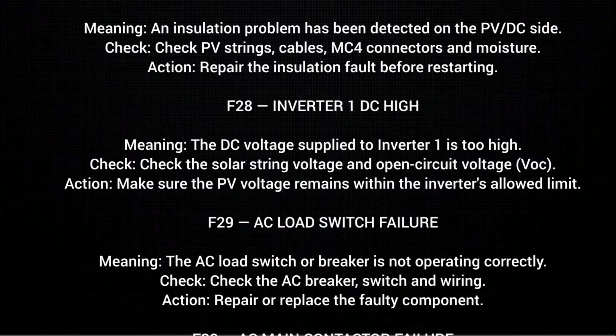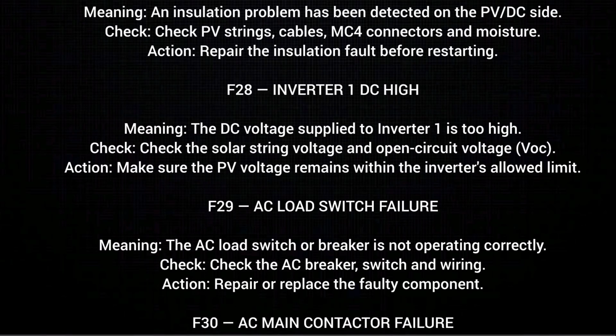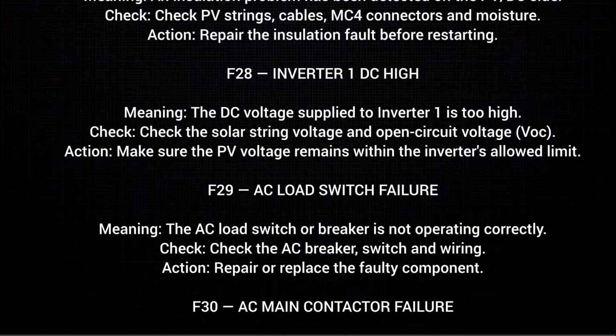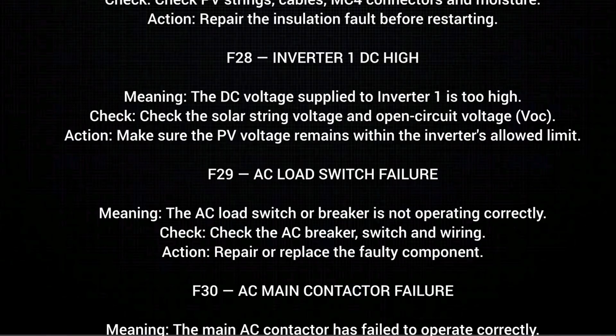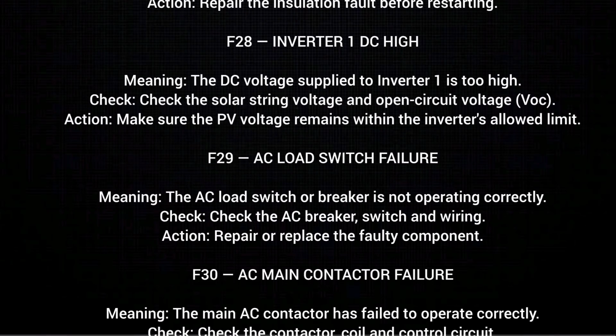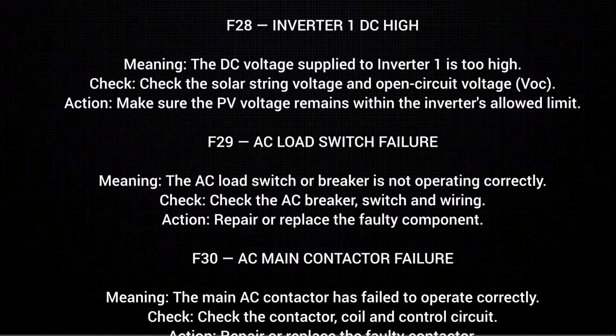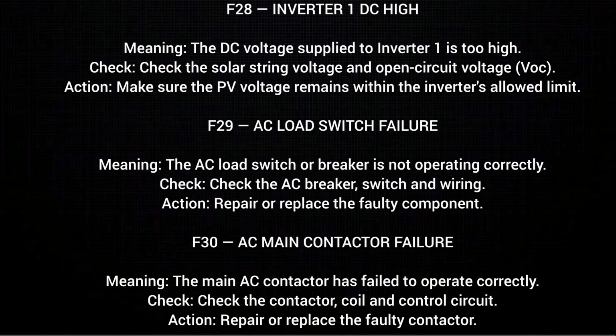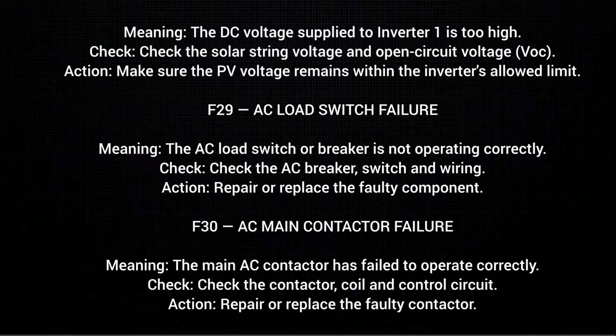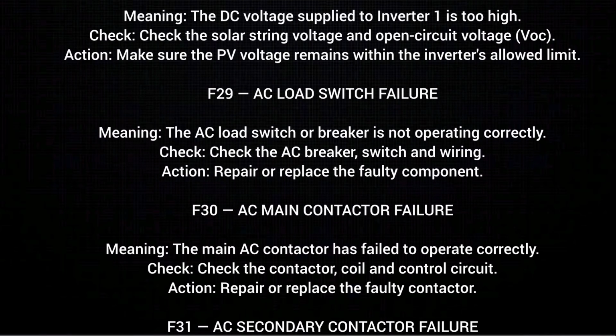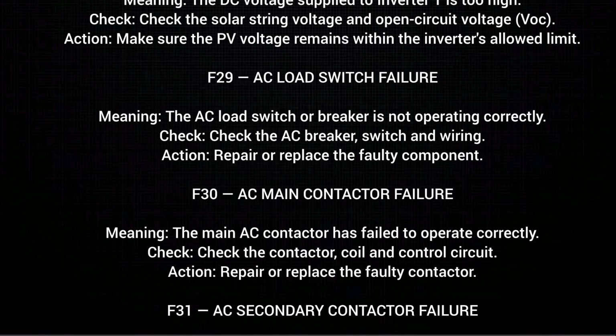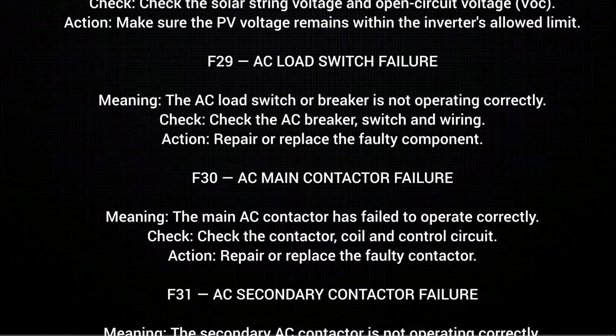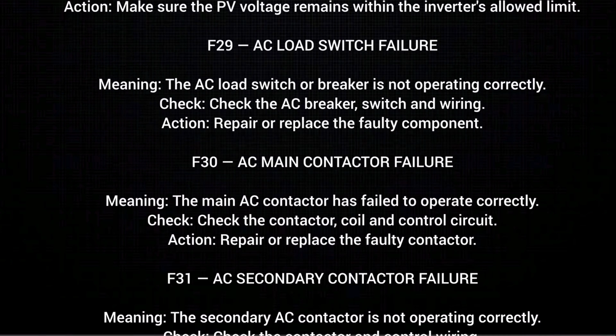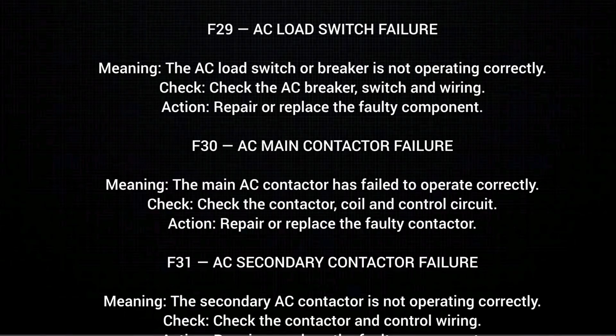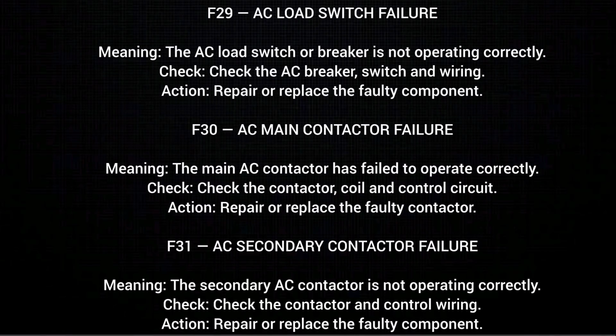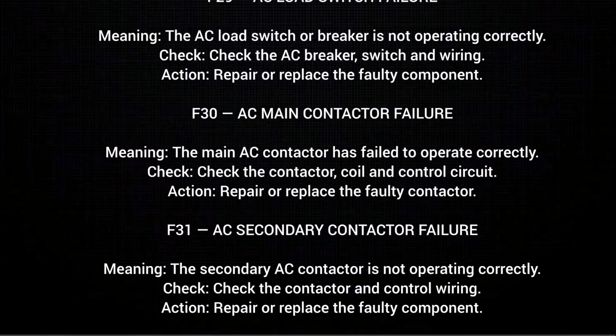F28. Inverter 1 DC high, meaning the DC voltage supplied to inverter 1 is too high. Check. Check the solar string voltage and open circuit voltage VOC. Action. Make sure the PV voltage remains within the inverter's allowed limit. F29. AC load switch failure, meaning the AC load switch or breaker is not operating correctly. Check. Check the AC breaker switch and wiring. Action. Repair or replace the faulty component.